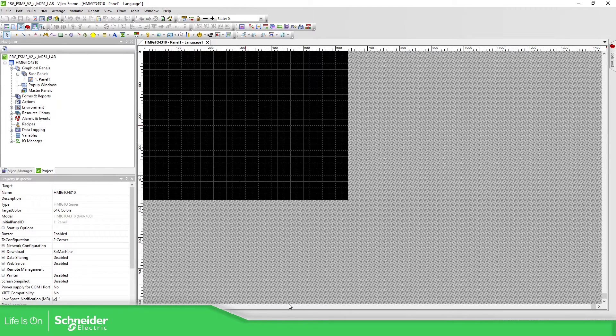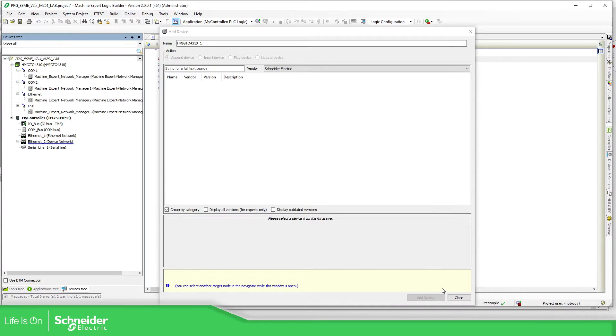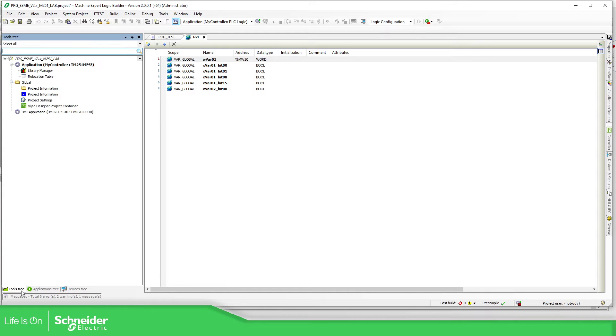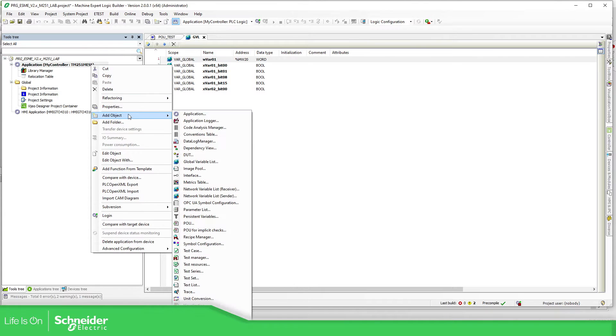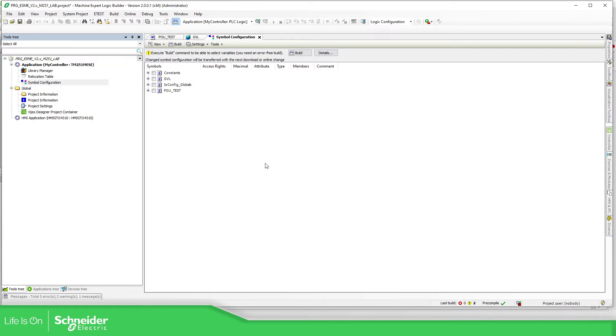Here you can see the component of Vijeo Designer. In order to share information from the PLC to the HMI, it's mandatory to add a symbol configuration. For that, we just need to go to the tools tree, on the application part of the PLC, right click, add object, and find the symbol configuration. We just name it and leave it as is. Once it is added, we just need to build.